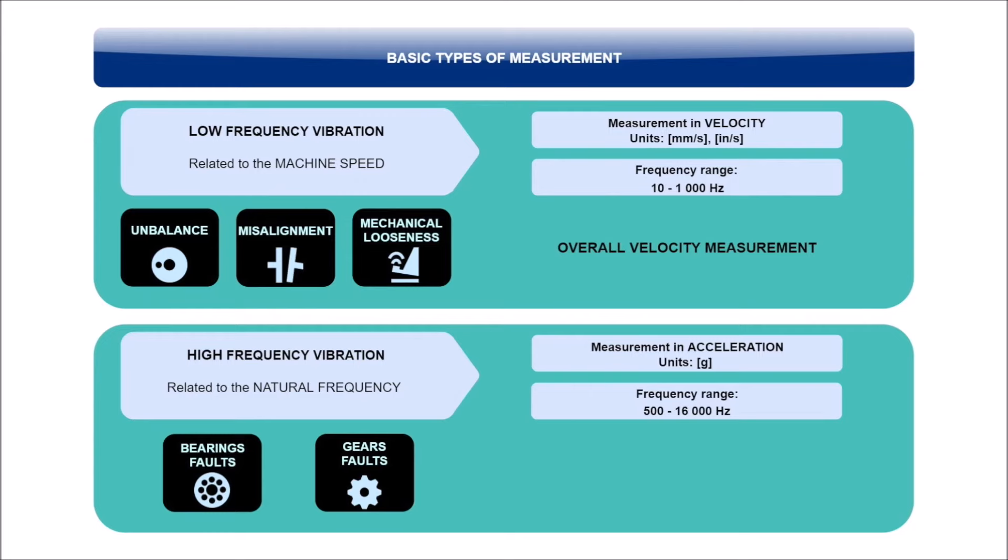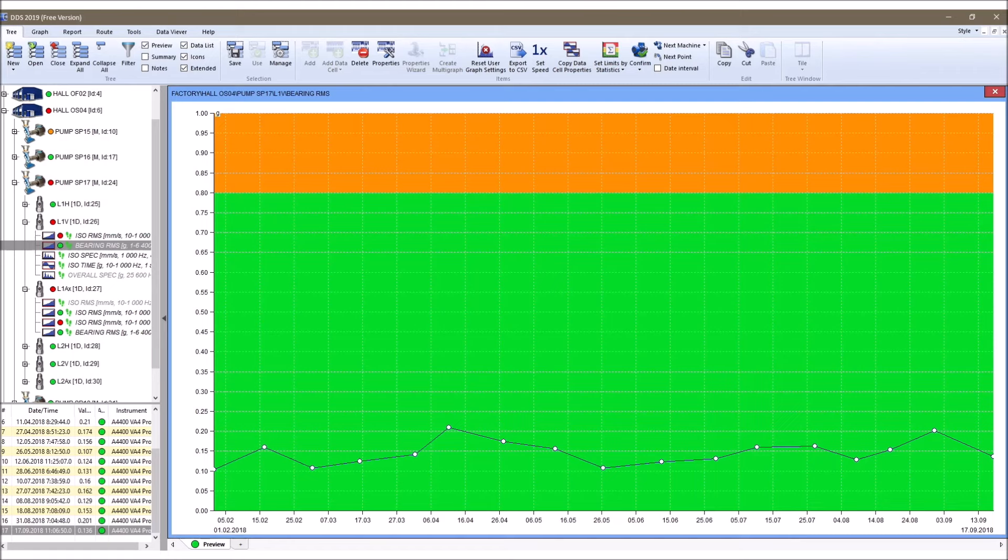So, the second measurement, which we will include in our regular machinery measurement, will be overall acceleration in G, in the range of 500 to 16,000 Hz. It is represented by one number. Again, using DDS software, we can trend this value in time and see its development.